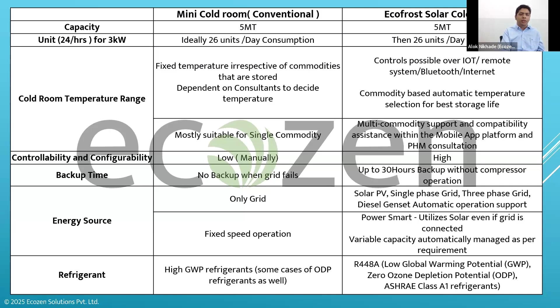Our focus is on sustainability, so we take this to the last mile - the choice of refrigerant itself is R448A, which is a low global warming potential refrigerant with zero impact on ozone depletion. It is also an ASHRAE A1 class refrigerant, meaning it is non-flammable and non-toxic. So can it support the kind of demands that are there?